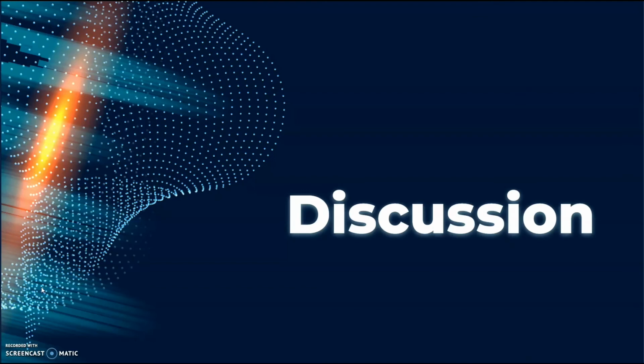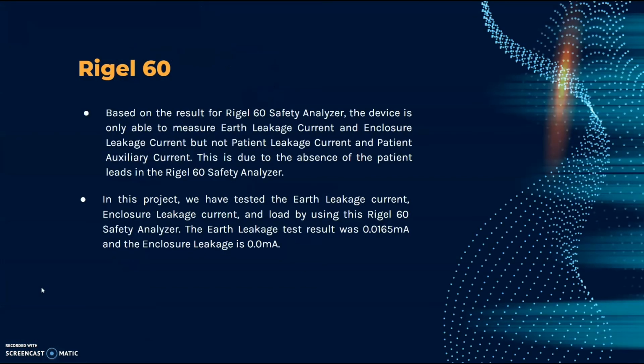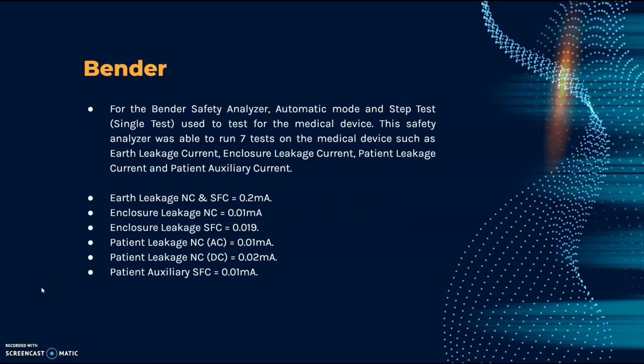My name is Abdullah and I'll be doing the discussion part. For the first device, Rigel 60, we were able to analyze the earth leakage current and the enclosure leakage current, but not the patient leakage current and the patient auxiliary current, due to the absence of the patient leads in the Rigel 60. The earth leakage test result was 0.0165 and the enclosure leakage is 0. For the second device, which is the Bender, we were able to do 7 tests, including earth leakage NC and SFC, enclosure leakage NC and SFC, patient leakage NC, AC and DC, and patient auxiliary SFC. You can see the results in front of you.